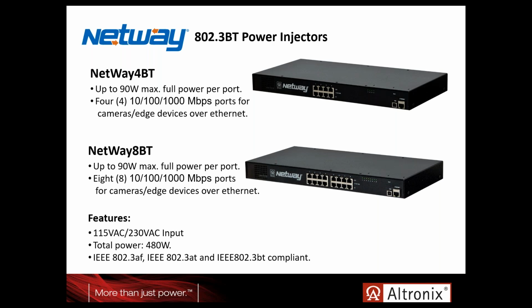What we're looking at here on the screen is our 4-port and 8-port version of our PSCs that work to the BT standard. These are power injectors only. What we're doing here is taking the data cables in from the existing switching equipment, and then injecting power on all 4 pairs of the cable to deliver up to 90 watts.